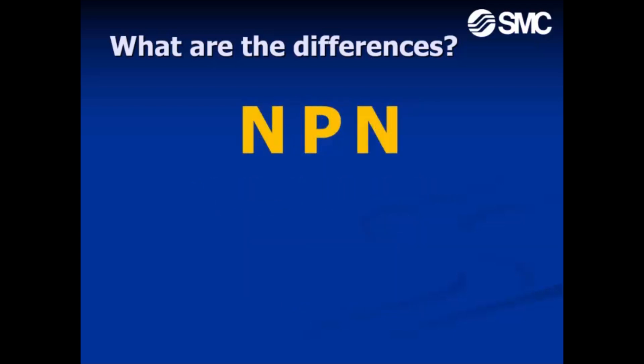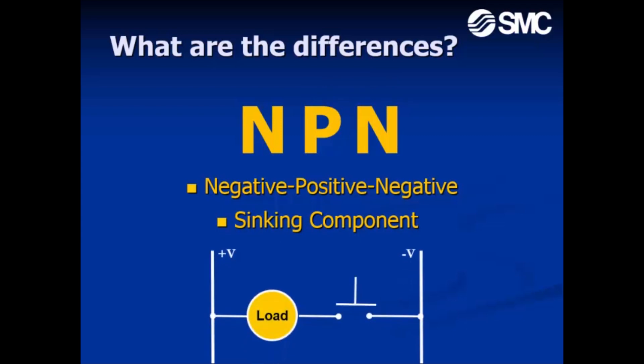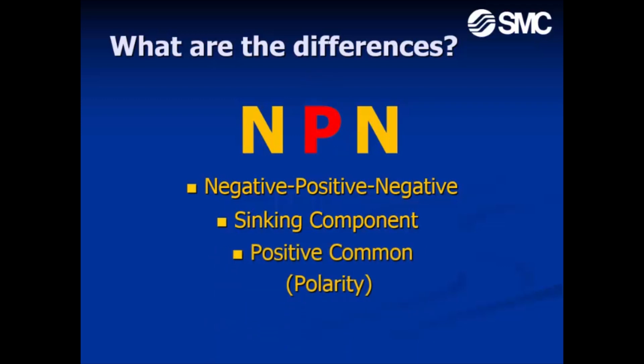Similarly, for an NPN circuit, NPN stands for negative, positive, negative. It is said to have sinking components. The switch controls whether the load has a connection to the negative common. The positive common connection can also be remembered by the middle initial P.